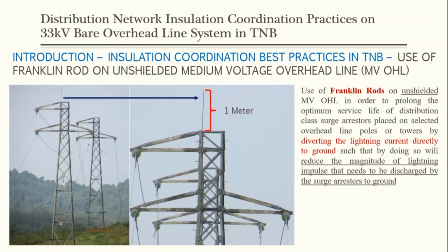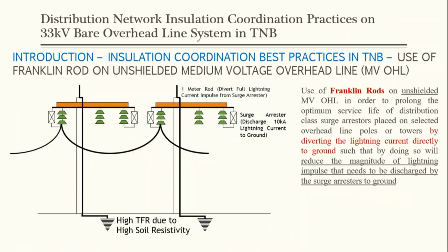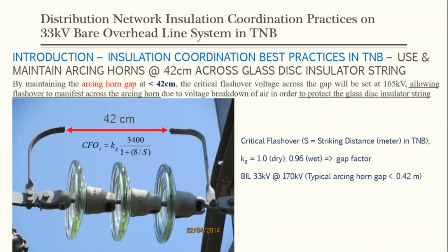We want to deviate the lightning surge so that it will go to ground without causing the surge arrester to do overtime work, so that we can ensure that the surge arrester can have a nominal service life, right? And the combination of the 1 meter rod and also the use of wooden cross arm at a high tower footing resistance area can eliminate, or not to say eliminate, can minimize the effect of lightning impulse on our system. Right.